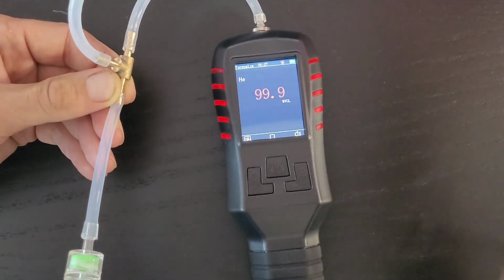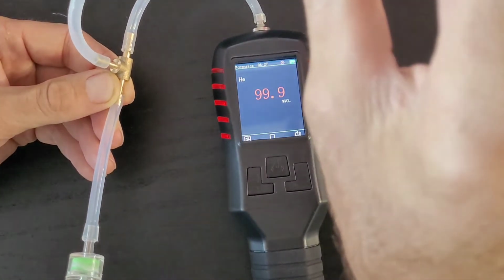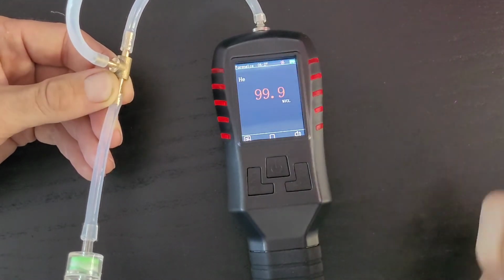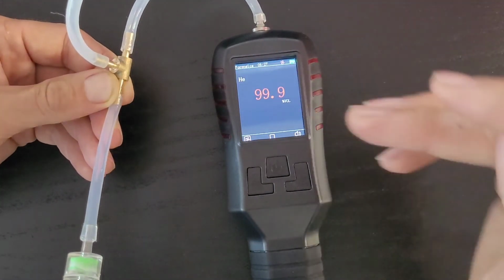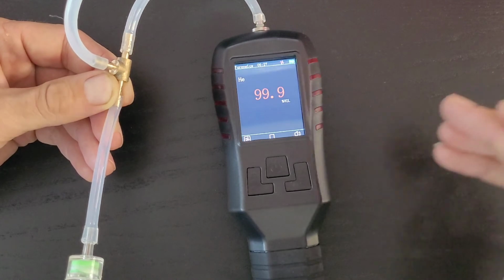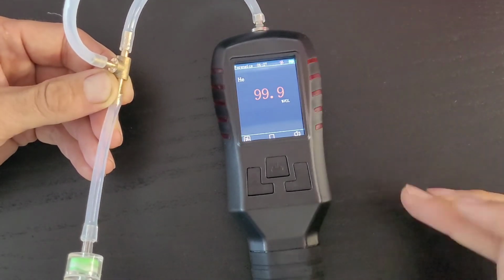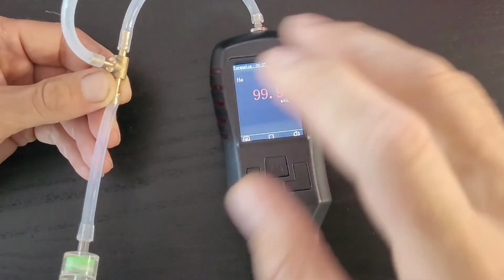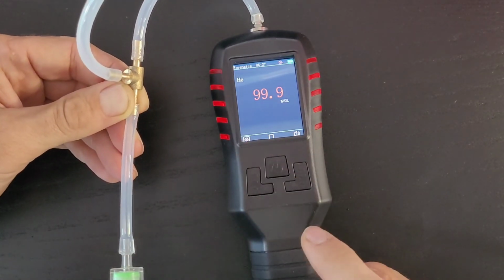Now, if you're using a 60% helium in air, you will put 60 when you span, or 75, or whatever the case may be, depending on your calibration gas of helium, okay, folks? That's the only difference. Very straightforward. Make sure you have your T-piece.